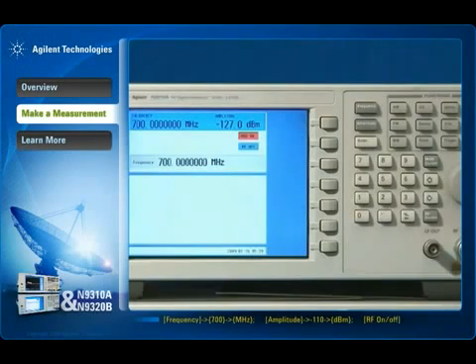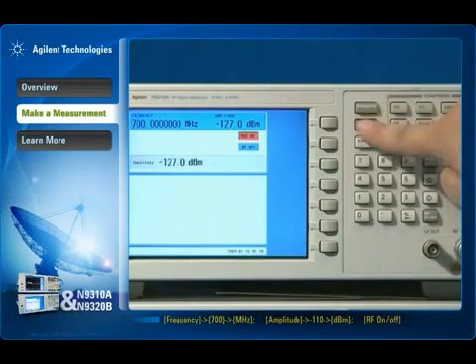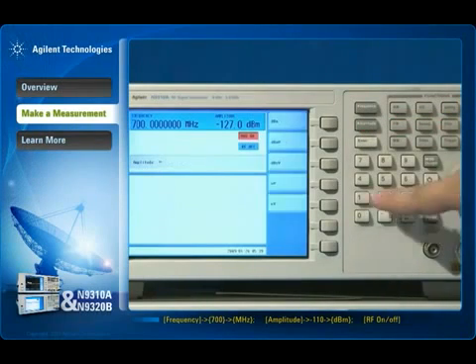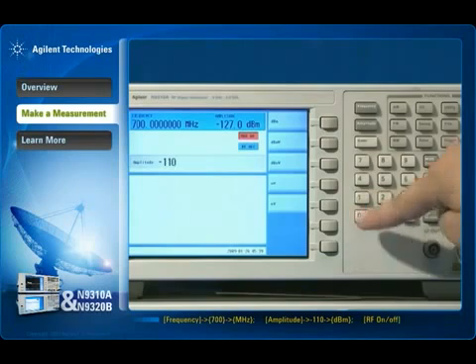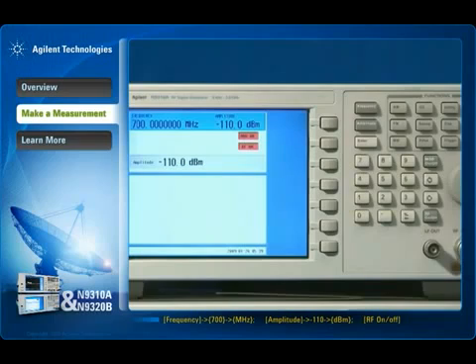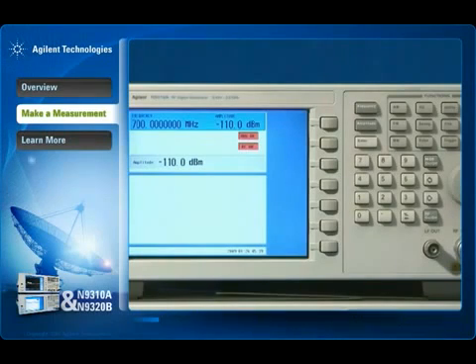If you want to measure a low level signal — for example, a minus 110 dBm signal — the N9320B option preamplifier is helpful. It improves the instrument's sensitivity to detect lower level signals such as spurs and harmonics.